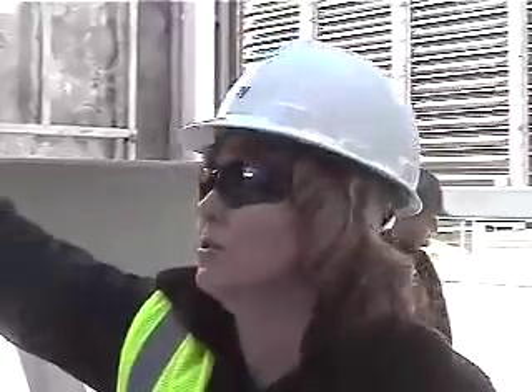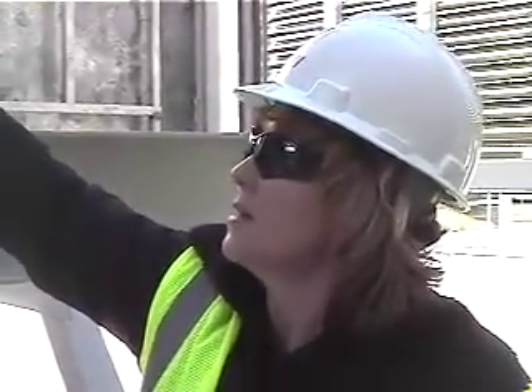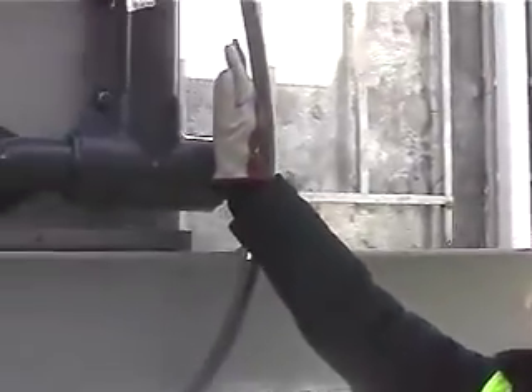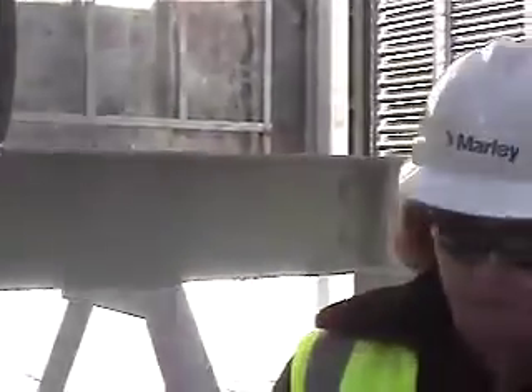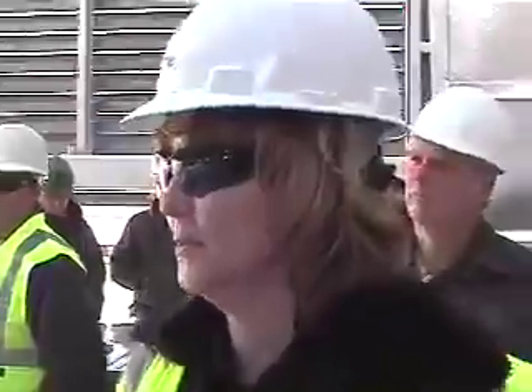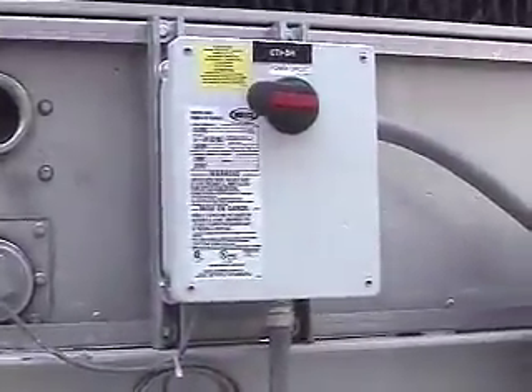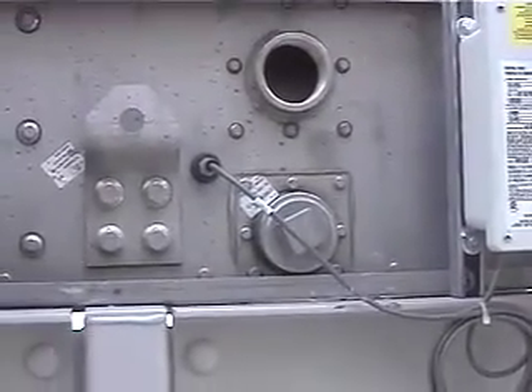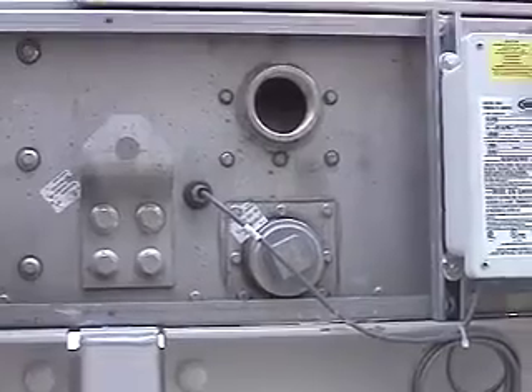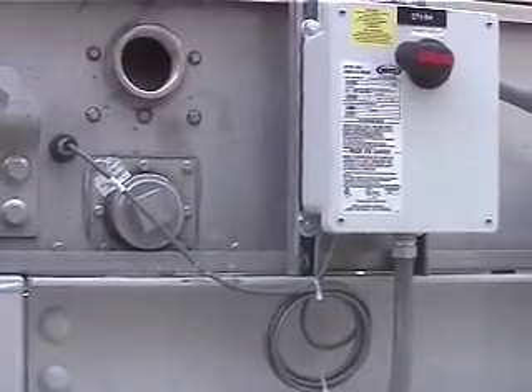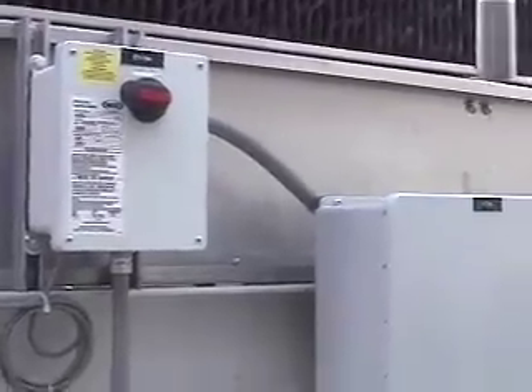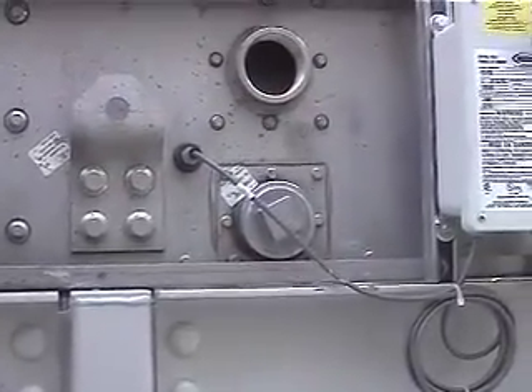This is water level control. That just has a makeup probes and probably low or high water shutoff. That's the control panel for the basin heater, right there. Over to the left is the probe to the wire coming out. It measures the temperature and makes sure there's enough water in the cooling tower for the heater to come on. Right below that is the element, the basin heater element.